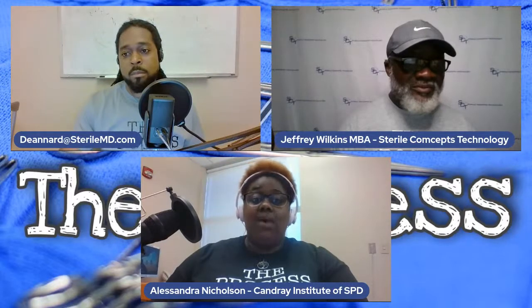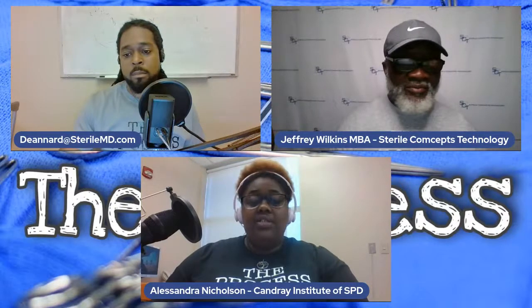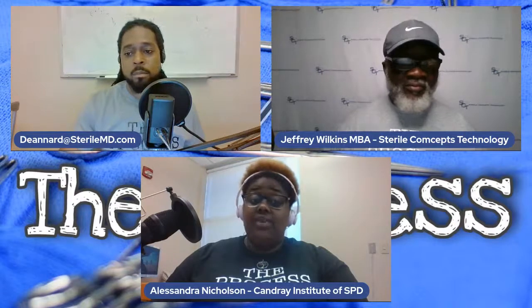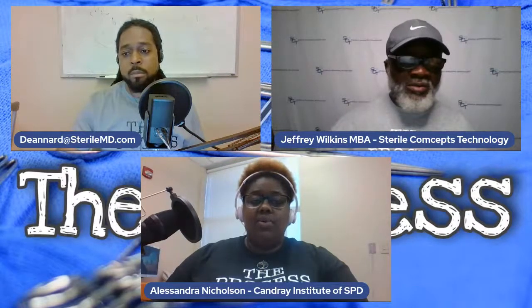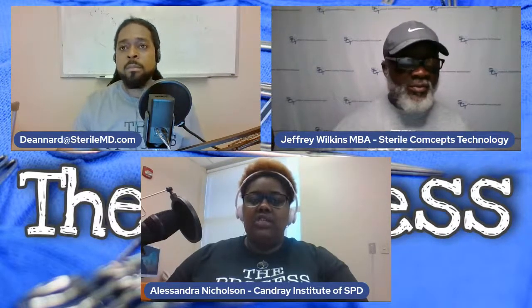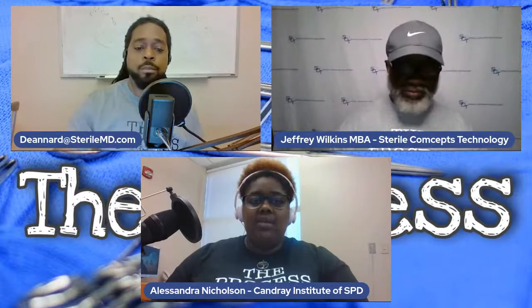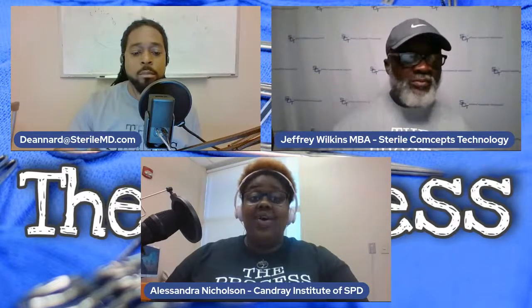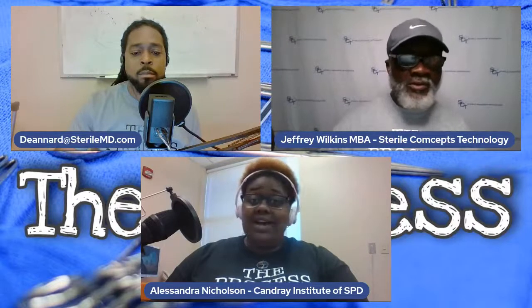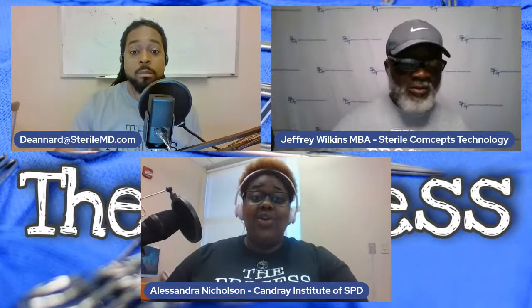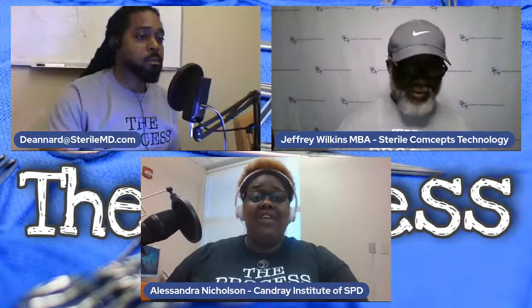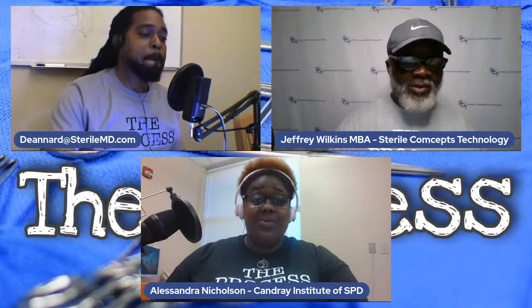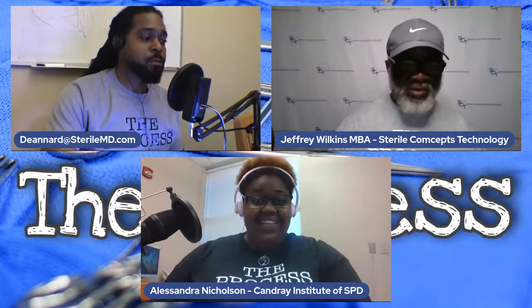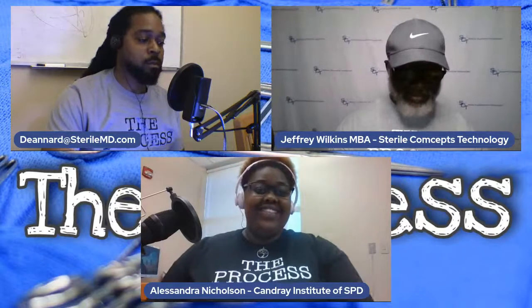I found a major problem with one of mine a couple months ago, and the only way I was able to get it resolved was by putting in a MedSun report, and the company actually then took me seriously and had a meeting and came back with the clinical information. But it was a whole IFU with no dry time, and that clinical director was arguing with me that we did the 510K process, and who are you to ask me where the dry time is?